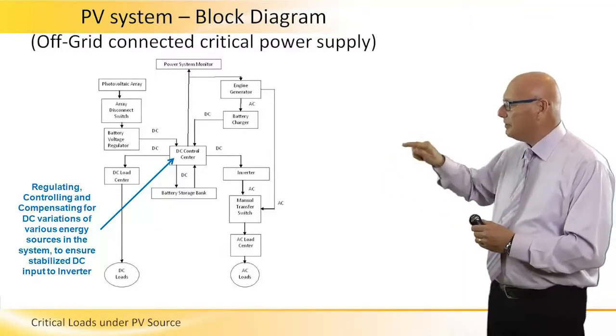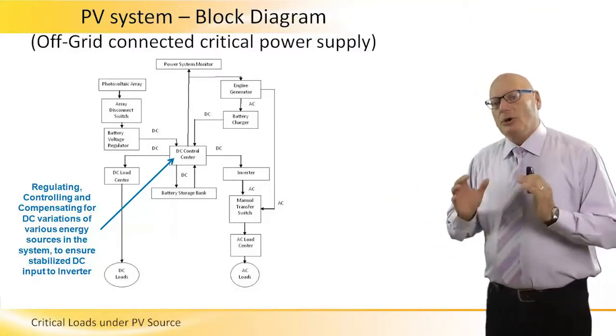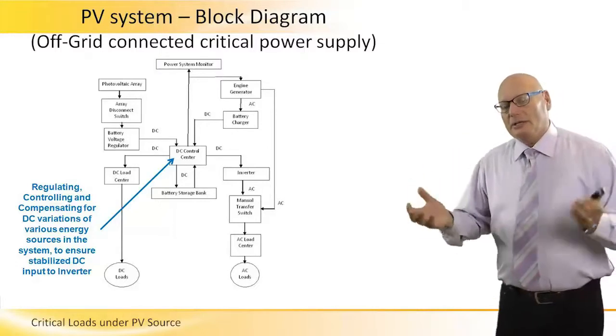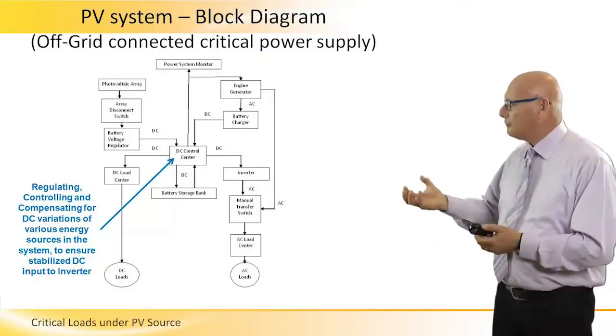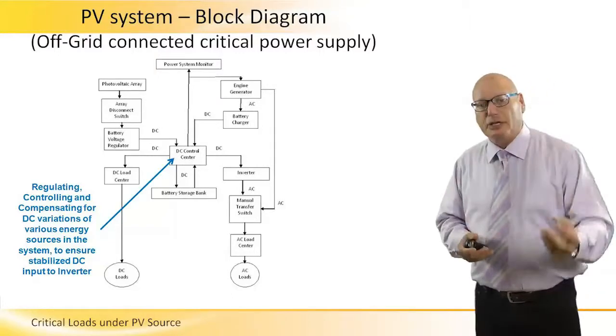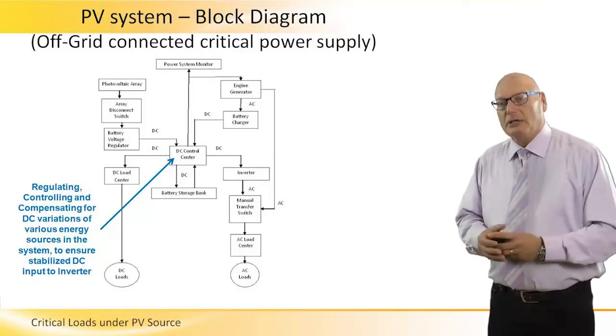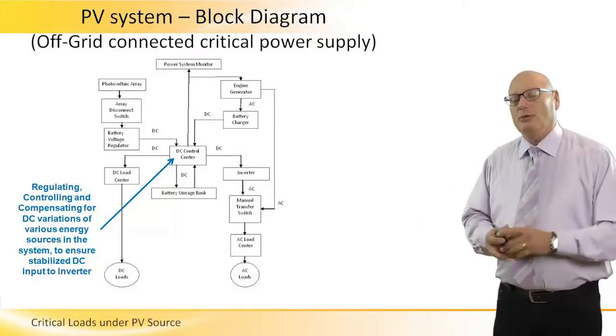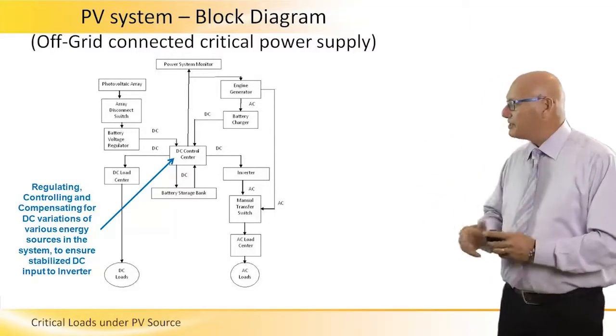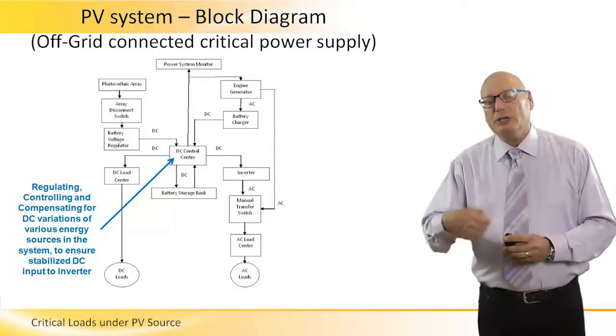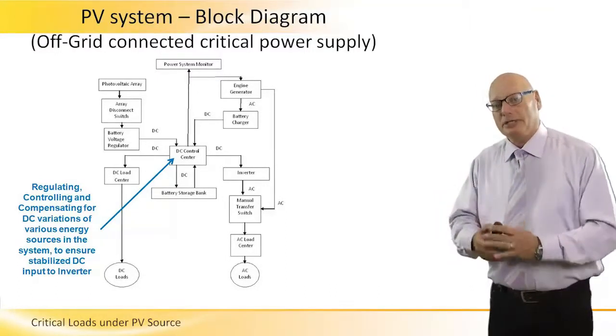The engine generator bypasses the battery charger, bypasses the inverter, and goes directly to the transfer switch. So although we have hybrid systems — some energy coming from the generator, some energy coming from a renewable PV array (photovoltaic; renewable can also be wind) — the engine generator can bypass all of them, go to a switch, and go out to an AC load. That's for critical applications.